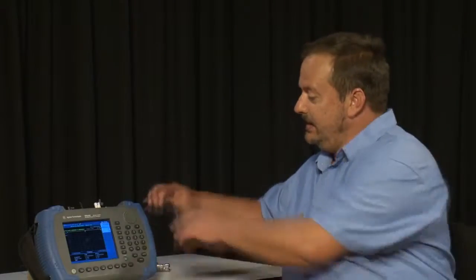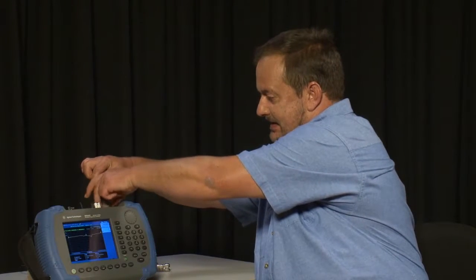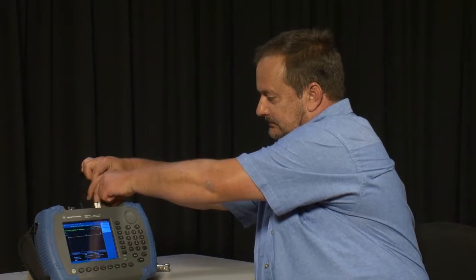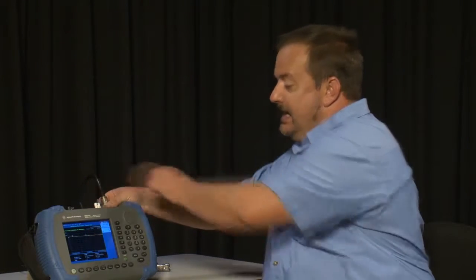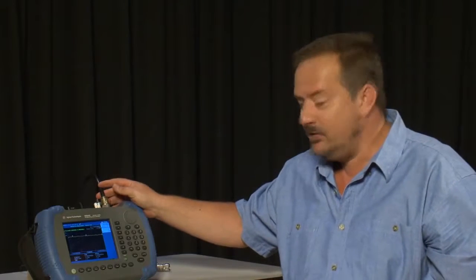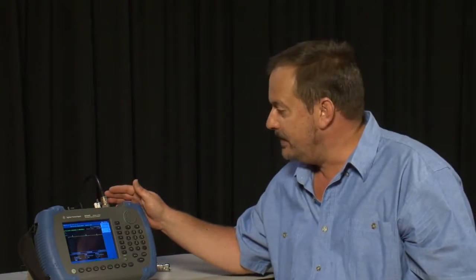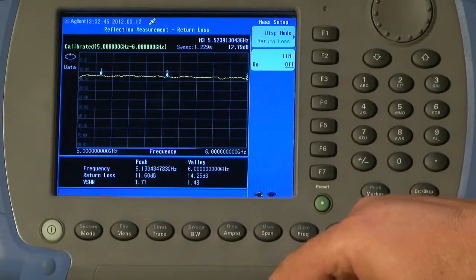So all I need to do is connect my cable to the HSA. And because we want to test this cable over the same frequency range that we tested the antenna in the previous measurement, I do not need to perform another calibration. It says the instrument is already calibrated between 5 and 6 GHz. All I have to do is press the Meas key and select one port cable loss.